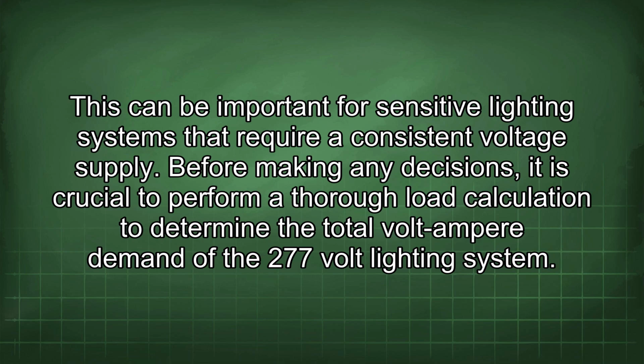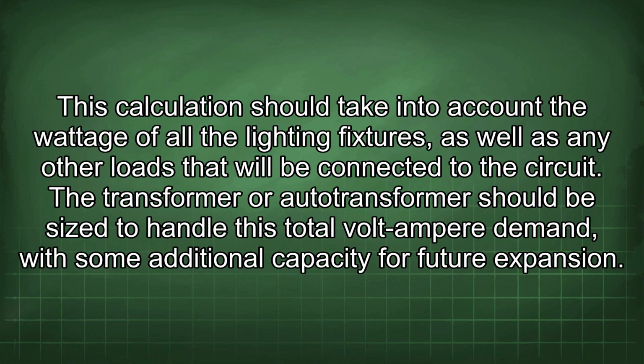Before making any decisions, it is crucial to perform a thorough load calculation to determine the total volt-ampere demand of the 277 volt lighting system. This calculation should take into account the wattage of all the lighting fixtures, as well as any other loads that will be connected to the circuit. The transformer or autotransformer should be sized to handle this total volt-ampere demand, with some additional capacity for future expansion.